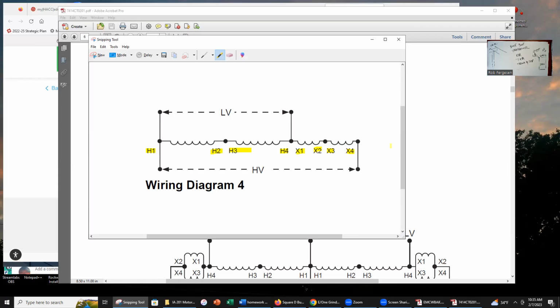All right, so in order to get my output voltage of 208 with an input voltage of 240, what I need to do then is wire in my input here. So this is leg 1 in, being attached to that point, and then my leg 2 in is being attached to that point. So what I'd be doing essentially is giving my high voltage in, I'll take my low voltage out. So my leg 1 out would be attached to that point, and my leg 2 out would be attached to that point. So that gives me my output voltage of 208. In other words, drop it by 32 volts.